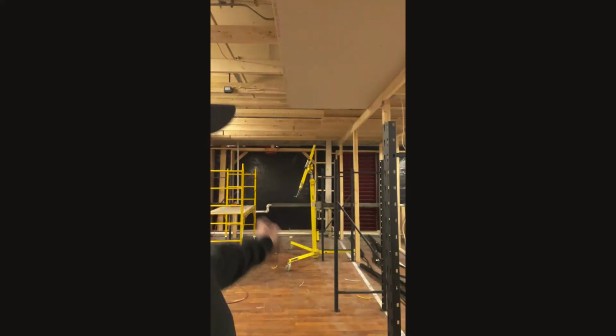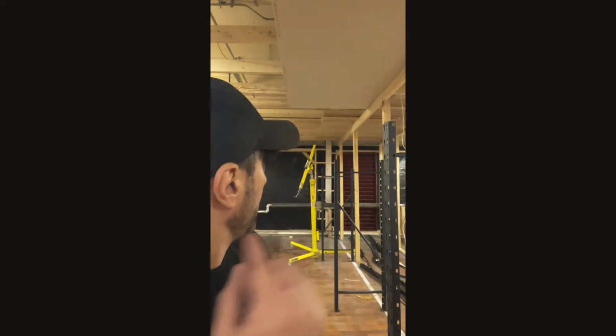Okay, so why they're changing the layout right now is for airflow. Back there behind me is that black tarp. That's the wall that we knocked out. That's where those giant fans are gonna go. Back there, the fans are gonna suck air outside. You see they're putting sheetrock on the ceiling. They're effectively building a giant wind tunnel in here. These racks right here are where the equipment's gonna go, so the whole center area is gonna be all equipment. These sidewalls here are effectively gonna create an area to walk behind the equipment to easily access the back side of it, and then there's going to be a small hallway sheetrocked off, fresh air in from the sides coming in to the center to feed, sucking out the back. Giant wind tunnel. When this is all done, it's going to be awesome.